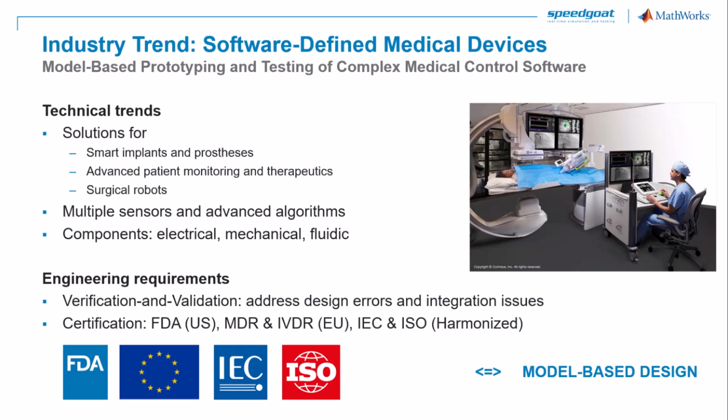And it is these requirements that matter to key industry stakeholders, government regulators, scientific advisors, healthcare providers, and ultimately end users, patients and clinicians. Model-based design for medical control software ensures that requirements can be traced to models, code that is automatically generated from models, and tests that are needed to fulfill verification and validation tasks according to the certification standards.